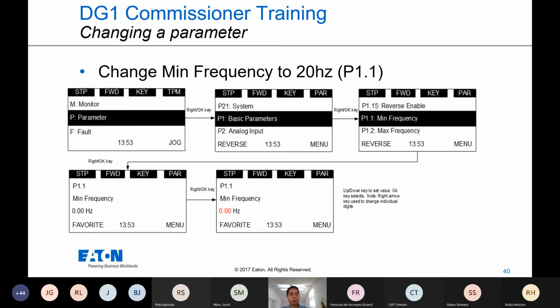One of the most important aspects here is to change your minimum frequency. Now, if you have a pump application, please do not change this to 20 hertz. This is mostly for a fan application. It is important that you look at your pump curve, communicate with your operator, and if the minimum is, let's say, 60%, that you go at maybe 36 or 40 hertz and have that as your absolute minimum every time your VFD starts.